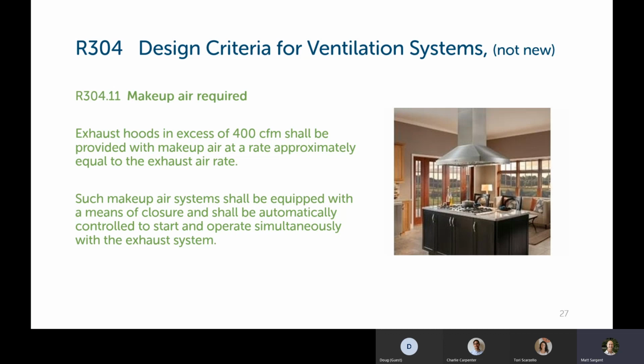So R304, this is also present in the 2015 code. We need makeup air for range hoods in excess of 400 CFM. And I will just say that this makeup air adds expense, and there's considerable energy penalty for introducing, I don't know, 400 to 1200 CFM of outdoor air every time the range hood is operated. These makeup air systems have to be interlocked with the range hood, and they need to have a means of closure.